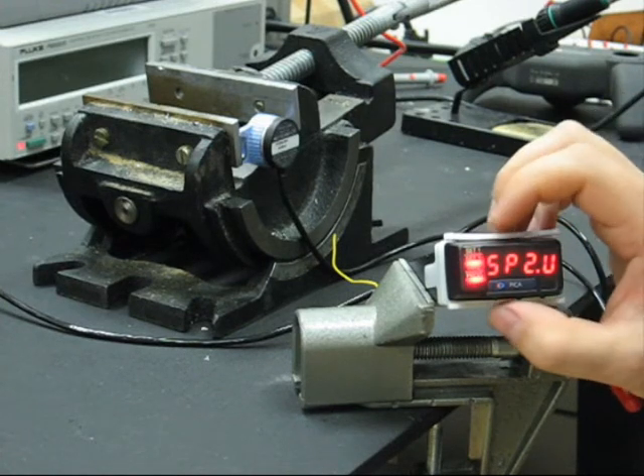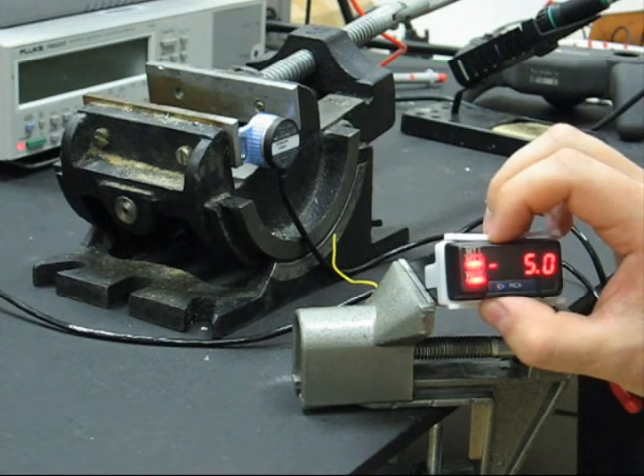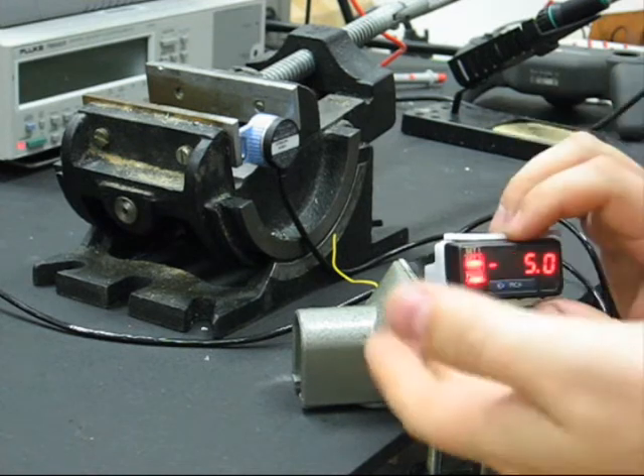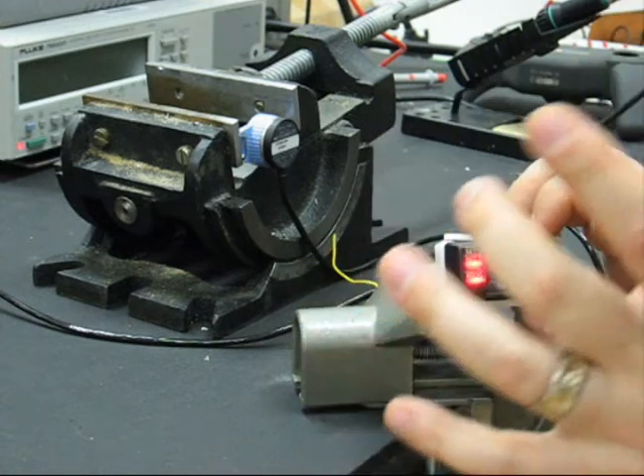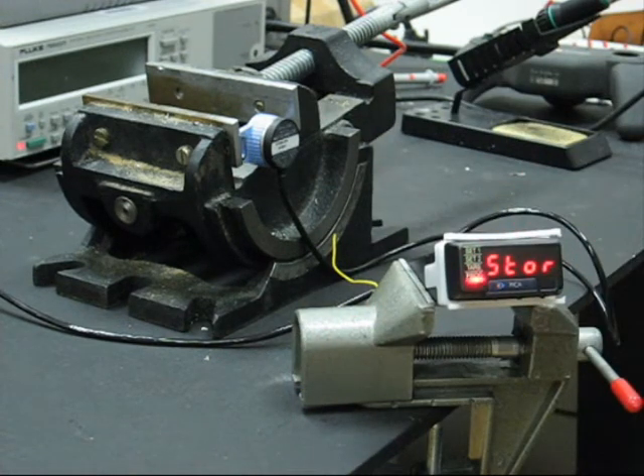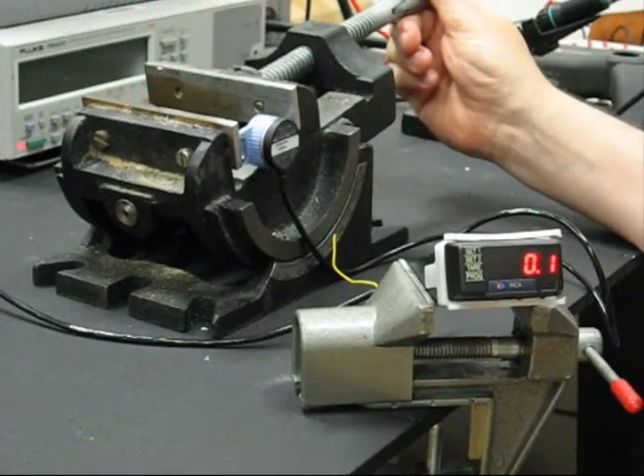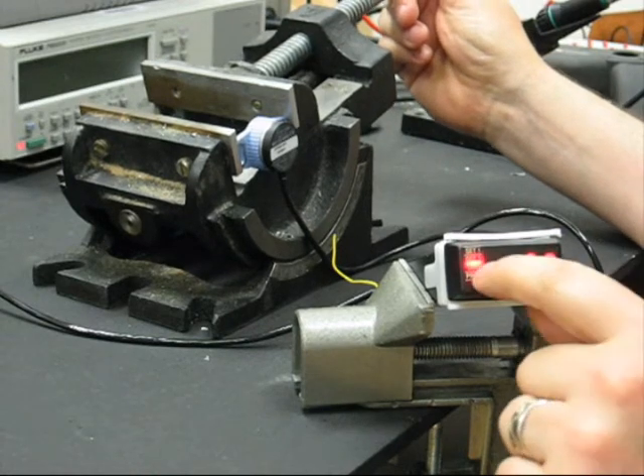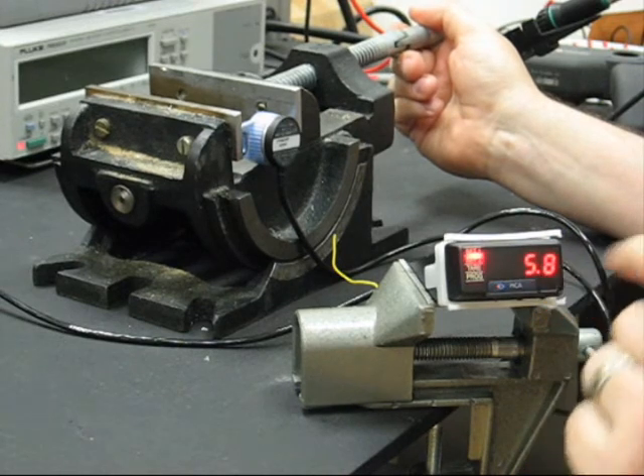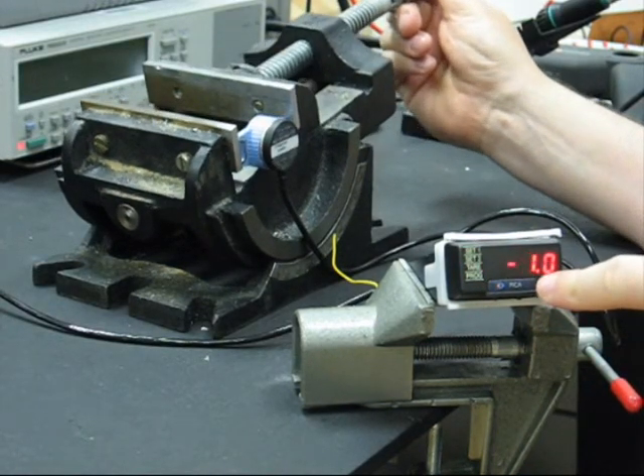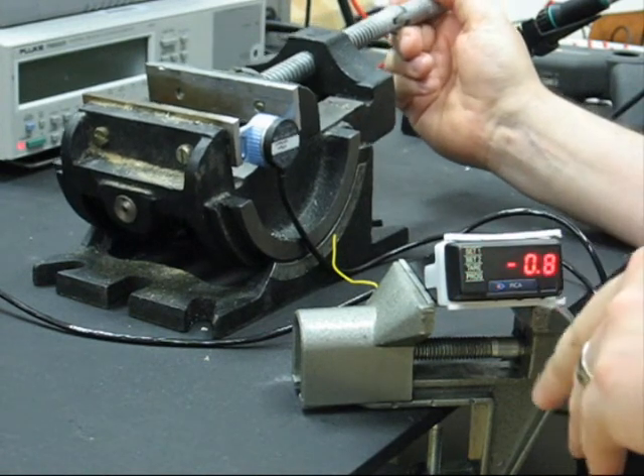Now, it's going to go to set point 2. And I'm going to keep it as a negative. Negative 5 volts. Again, you change these values like you did with the set points. Like, with the actual set of the range points. So, press store. So now, when I move, you can see at 5, set point 2 came on. And at 5, set point 1 came on. Actually, the other one was negative 5. So, there you go. Negative 5, set point comes on. And that triggers the relay. But it keeps measuring, obviously, for you.